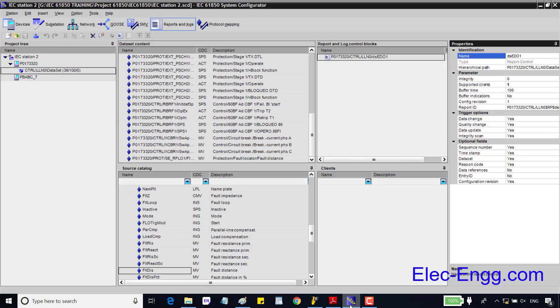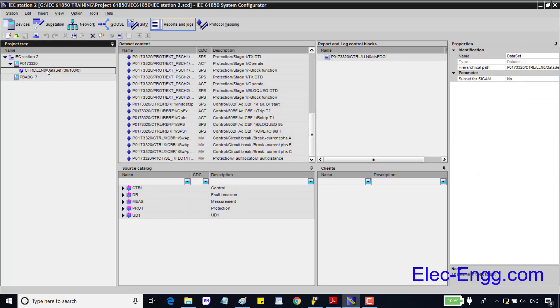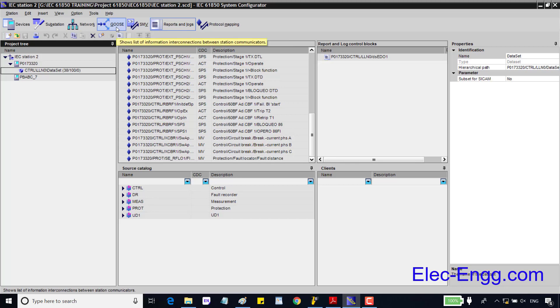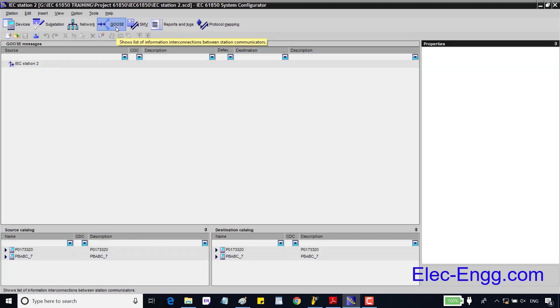In the previous session we created a dataset for the distance relay and added signals based on the dataset table. We should do the same for the other devices and create the datasets to add required signals. Next, we should create GOOSE datasets based on the project documents.